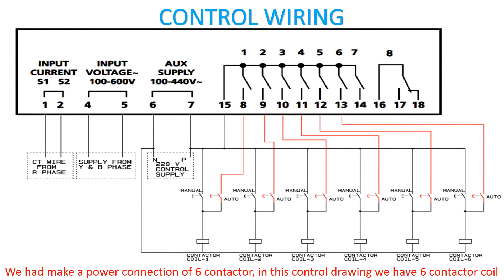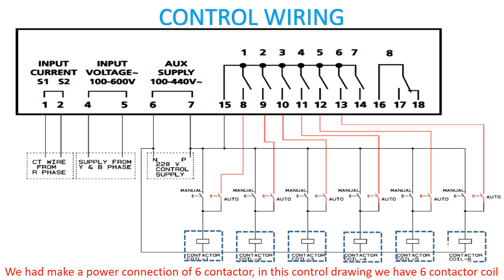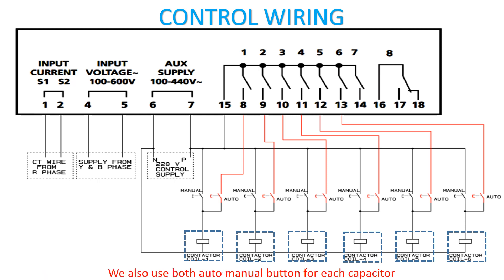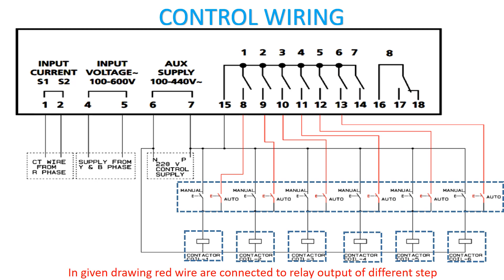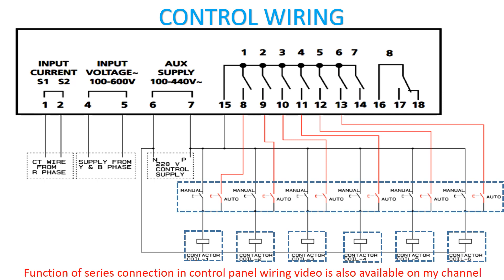We have made a power connection of 6 contactors, so in this control drawing we have 6 contactor coils. We also use both auto and manual buttons for each capacitor. The manual button is connected from the main control phase, and the auto button is connected with the relay of APFC. In the given drawing, red wires are connected to relay output of different steps. Auto and manual buttons are connected in series with the contactor coil.